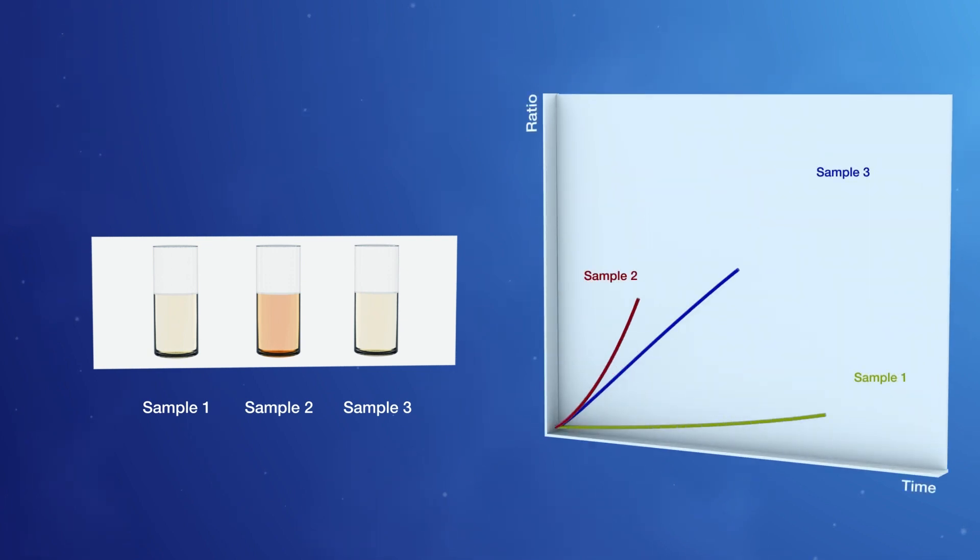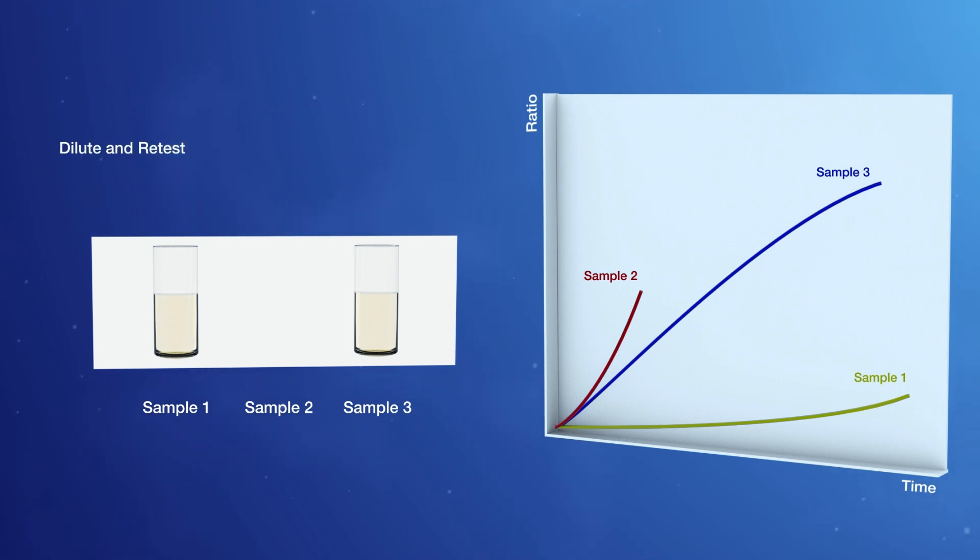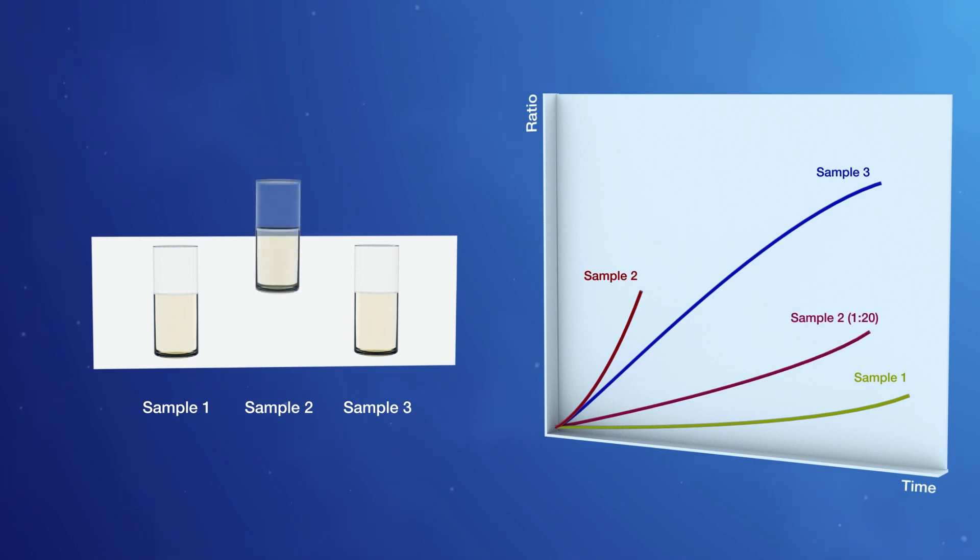Multiple detection events spanning the reaction incubation period determine early on if a reading is out of range. The identified sample can then be diluted and retested to avoid false negatives due to high analyte concentration.